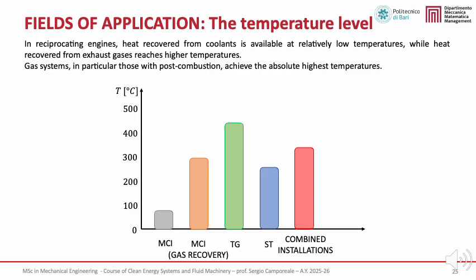or higher temperature applications. Gas turbine systems provide the highest exhaust gas temperatures among the technologies shown, especially when post-combustion or afterburning is employed. This makes gas turbines particularly suitable for high-temperature heat demand and for integration with bottoming steam cycles. Steam turbines, on the other hand, typically deliver heat at intermediate temperature levels, which are well matched to district heating networks and medium-temperature industrial processes.